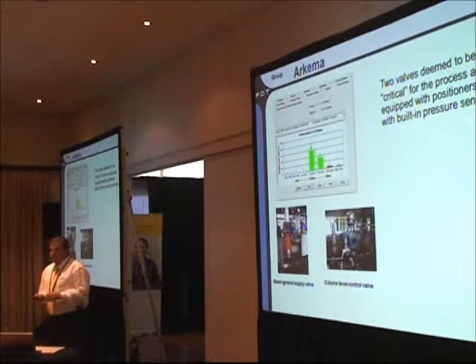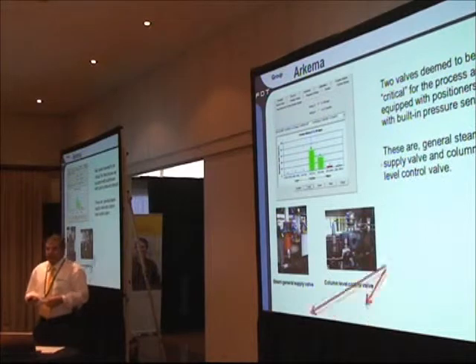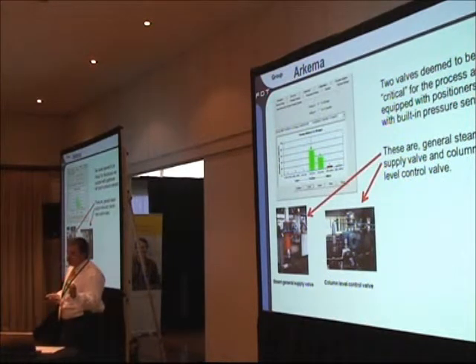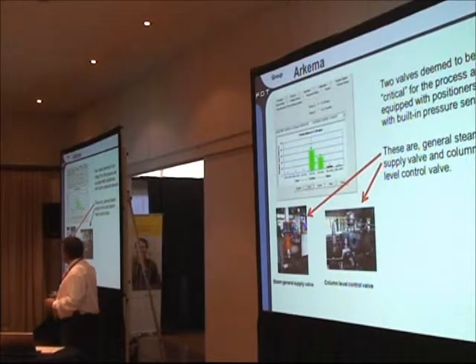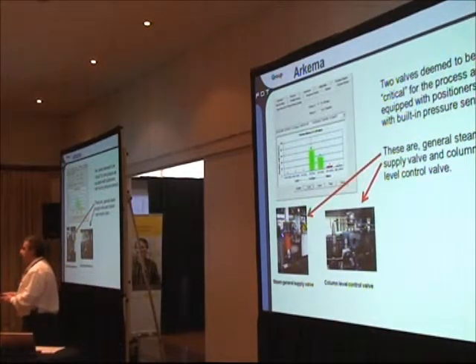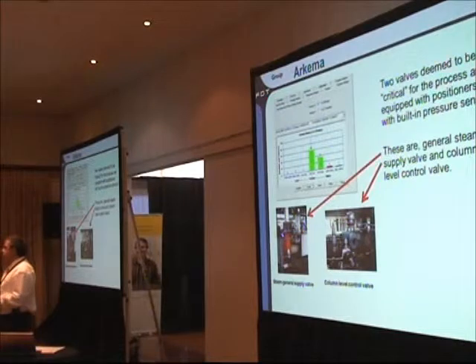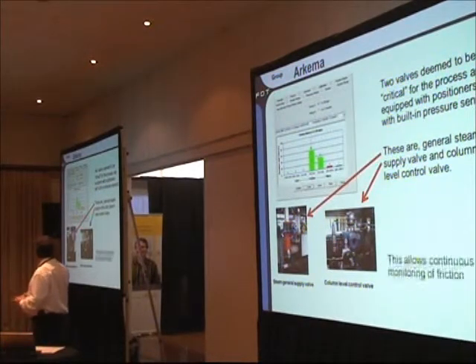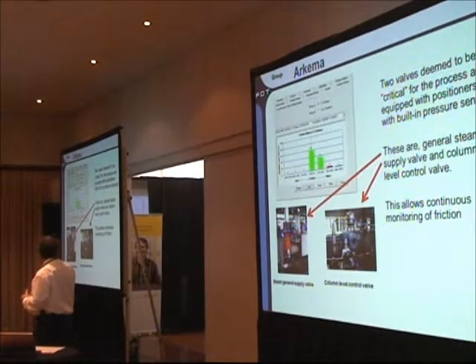There were two valves defined as critical: the general steam supply valve and the column level control valve. These were two valves which were really difficult to handle, where you really had to check continuously, and here the solution was continuous monitoring of the friction.